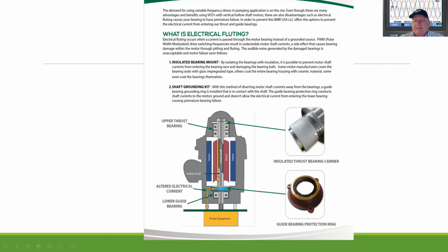Also, they isolate the bearings. They put insulated sleeves in the thrust bearings so that you don't get circulating currents in the upper bearings, and that ends up saving the life of the motor. They also, the type of insulation that's inside the winding, they've gone to spike resistant wire that makes the motors end up lasting longer.